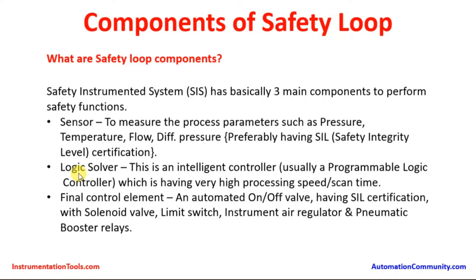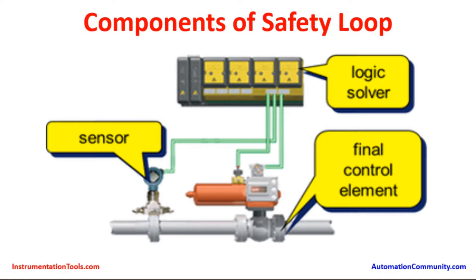The second component is the Logic Solver. This is an intelligent controller, usually a programmable logic controller, which has very high processing speed and scan time. The SIS logic solver has to act very fast depending on any hazard happening inside the plant, so the processing speed and scan rate for those processors shall be very high, and the logic solver has to be selected accordingly.